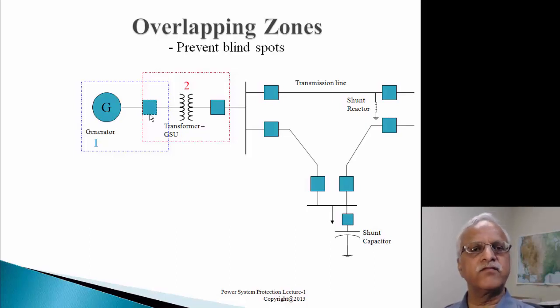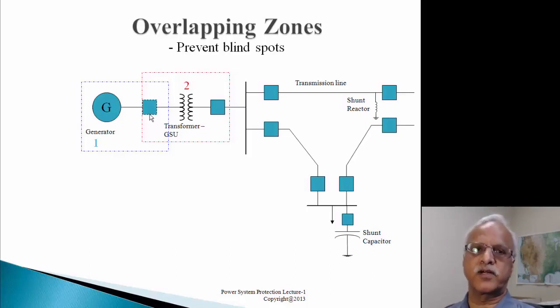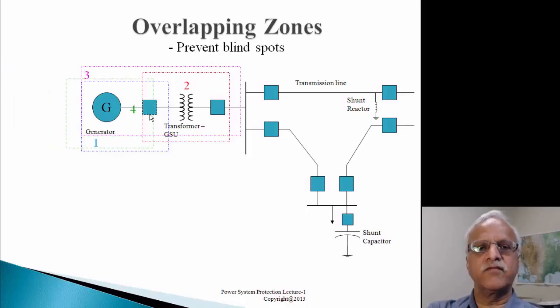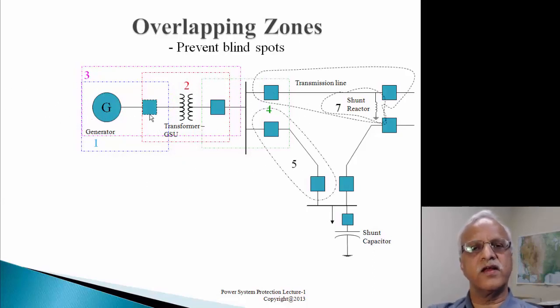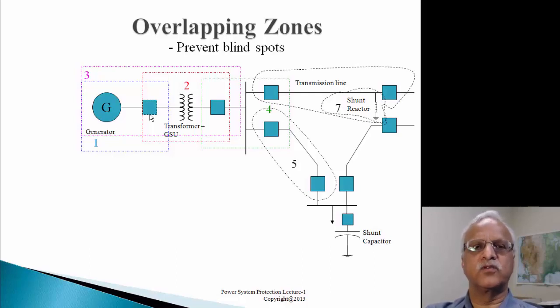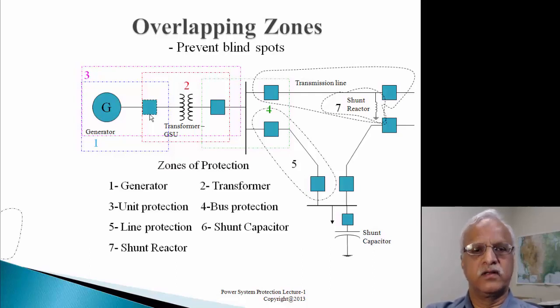As an example, if there is a fault within the generator breaker, both the generator protection and the transformer protection operate and isolate the faulted equipment. Looking at the previous slide, you will see there is no area without overlap - no zone that does not follow this overlapping rule.